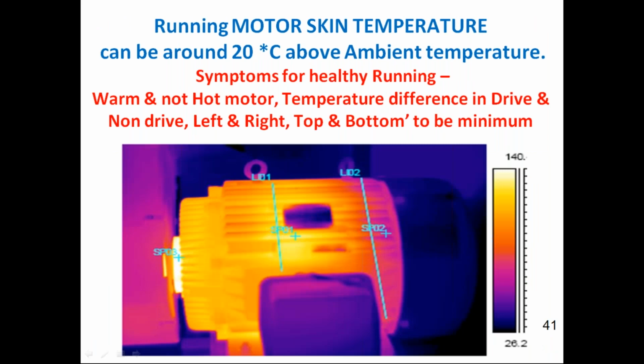As I was telling, the driven and non-driven temperature matters more in the given industry, because when the bearing is not healthy, the fins are given to the motor only to dissipate the heat load. But if it is not able to dissipate the heat, automatically the driven temperature is more than 20 degrees above the non-driven. It is a point of misalignment, a point of bearing getting bad, or a point of poor lubrication in the bearing. All these things can be addressed. Next, please.